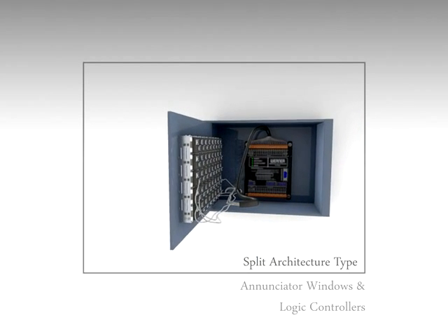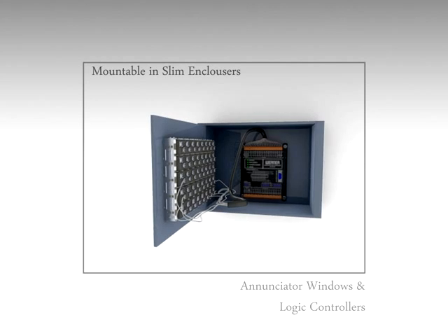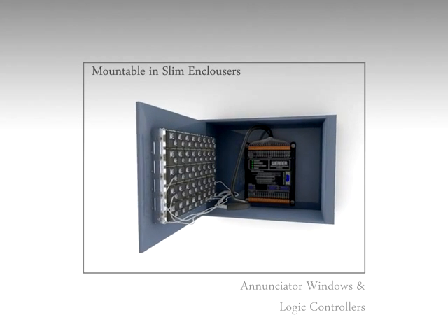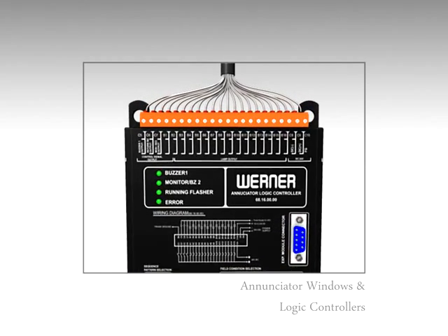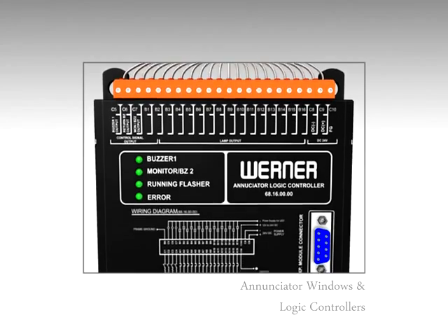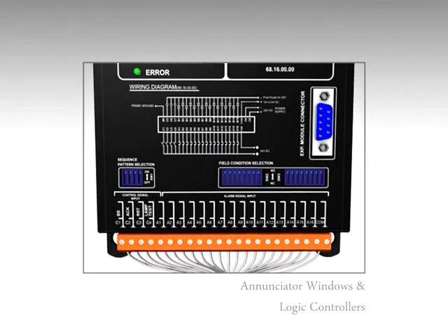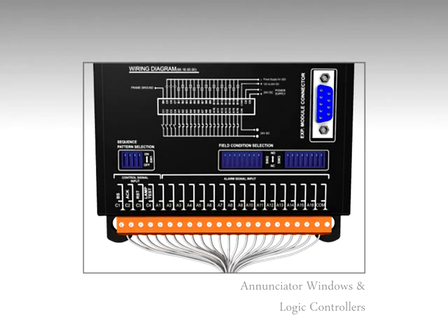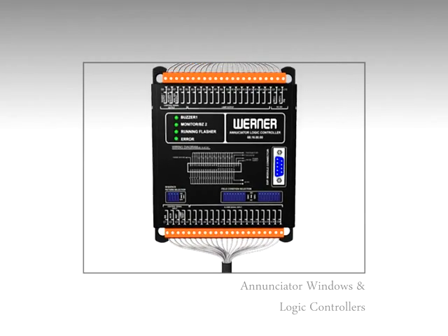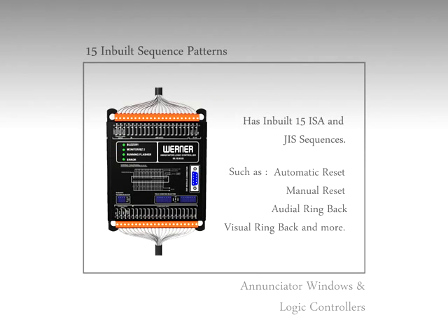Werner's 68 series annunciator logic controller is an ideal control circuit. These controllers are very small in size — 16 channels control is available in a small 5 inch by 5 inch size. Operating voltages can be 24, 110, and 230 volts. These are easily mountable on panel, and on the unit clear indication of error and status condition is provided to facilitate easy maintenance.